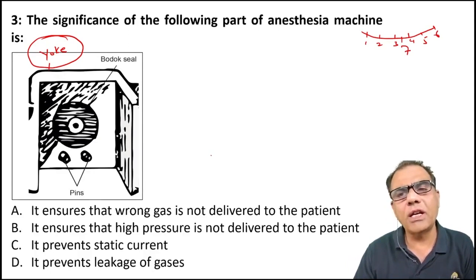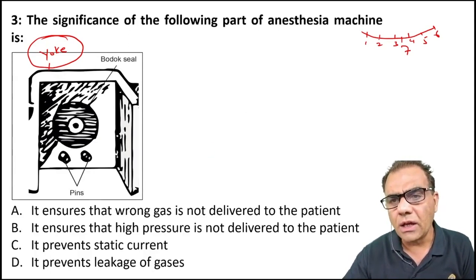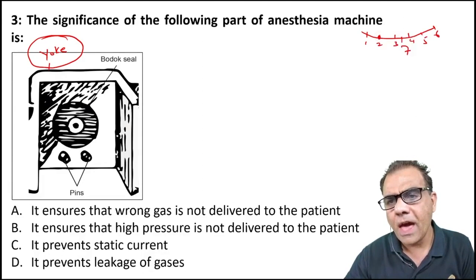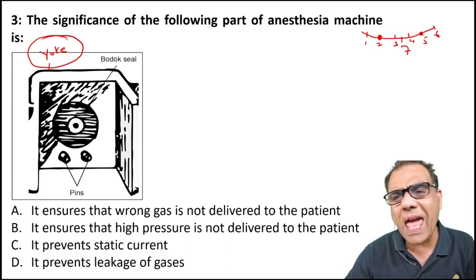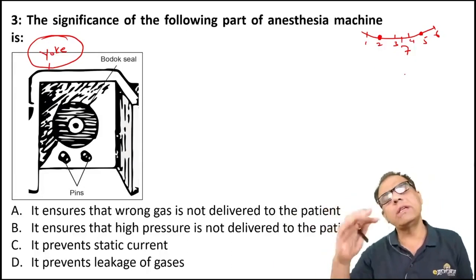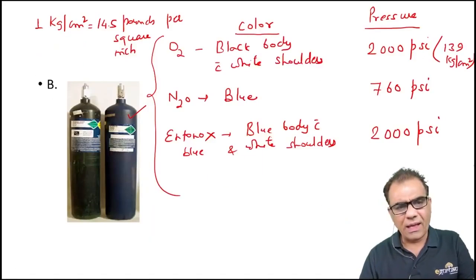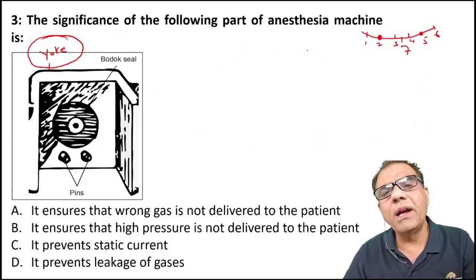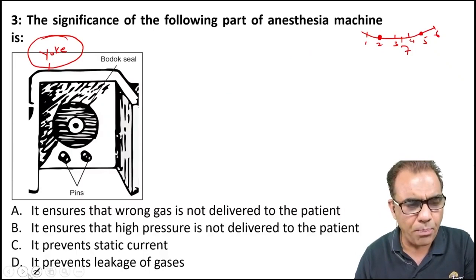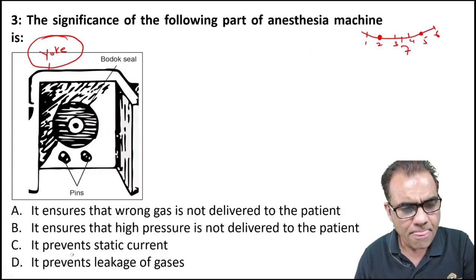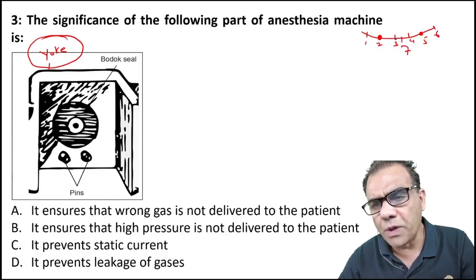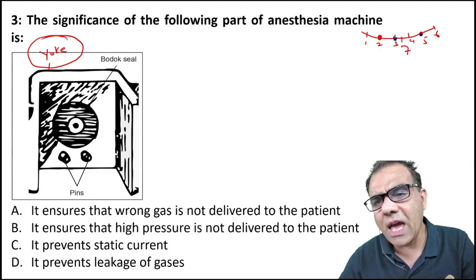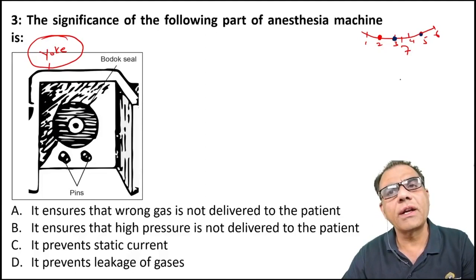Now we say that the pin index for oxygen is 2 and 5. That means the two pins at the yoke of oxygen will be at position 2 and position 5. Now at the same corresponding distance, there will be holes in the oxygen cylinder. Like here. Now we say the pin index for nitrous oxide is 3,5. That means at the yoke of nitrous oxide, the two pins will be at position 3 and position 5. And at the same corresponding distance, there will be holes in the nitrous oxide cylinder.